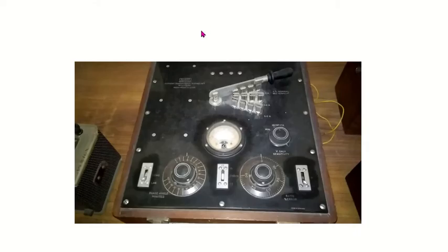If we look into the CT testing kit, we'll observe that there are certain control keys on the panel as well as some control rheostats. We'll look into what they are. This rheostat is used to control the phase angle, while this one is used to control the ratio error. Then here is a knob that controls the galvanometer sensitivity, and then we have this display for knowing the current that flows through the circuit.